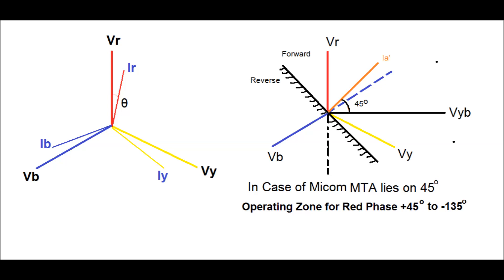Here, theta is the power factor angle for the normal loaded condition. Now, during a fault at R phase, the voltage at R phase will fluctuate — that is, the voltage will dip. For the healthy phases, Y phase and B phase, that is yellow and blue phase, are healthy phases. Therefore, a reference voltage is taken from the healthy phases for determining the proper direction of the fault location. That is, the reference voltage for red phase fault is taken as VYB, the voltage between yellow and blue phase.